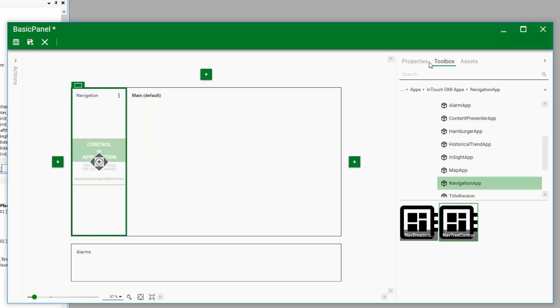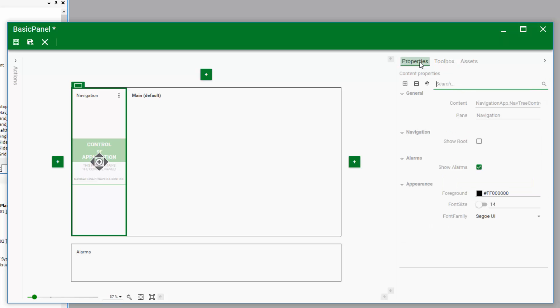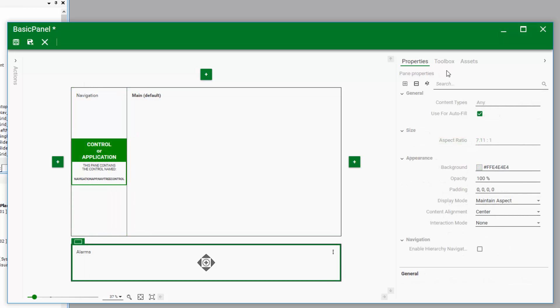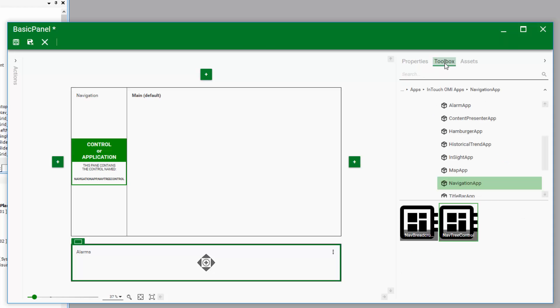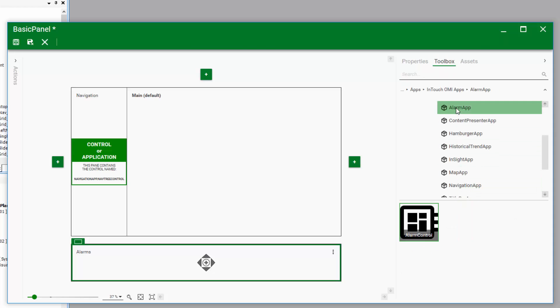The tree control has some configuration options we can set — like whether the navigation panel should start at the root of your galaxy model hierarchy, or at some other level or area that you define. We'll enable the showing of the root component and leave everything else at the default. We're going to do something very similar for the alarm panel — selecting it using the toolbox and the OMI apps, grabbing the alarm control, and sliding it over and dropping it in that panel.